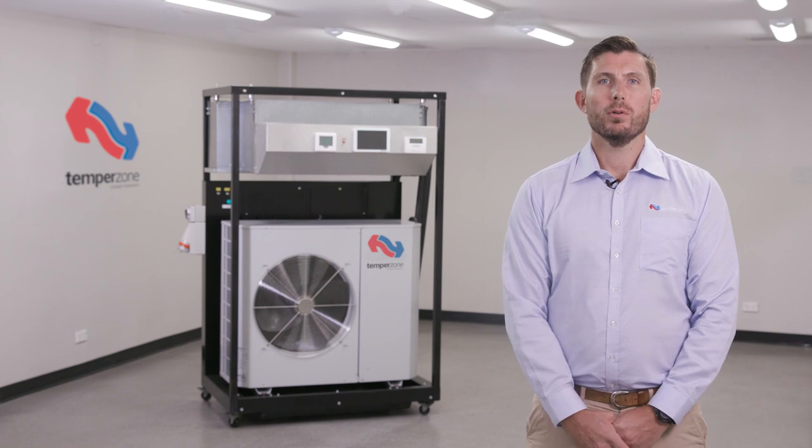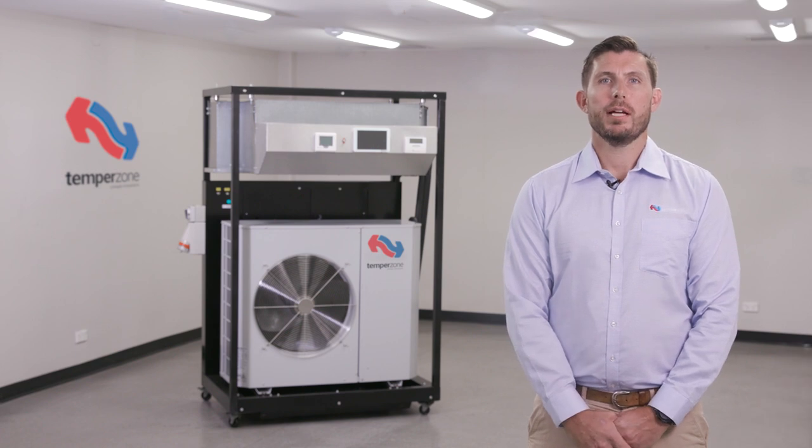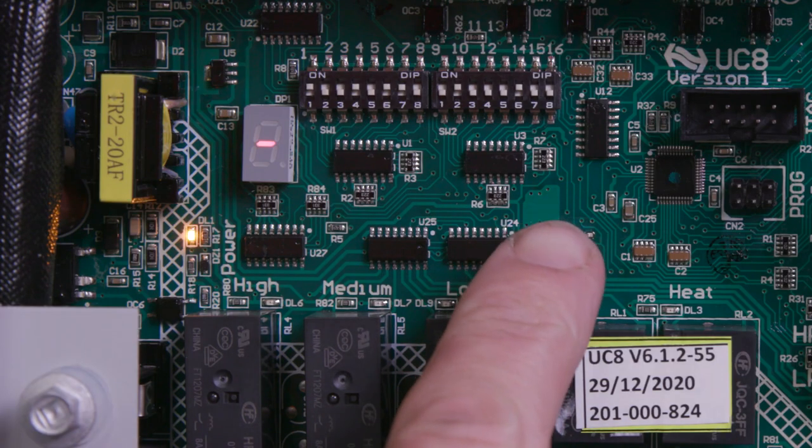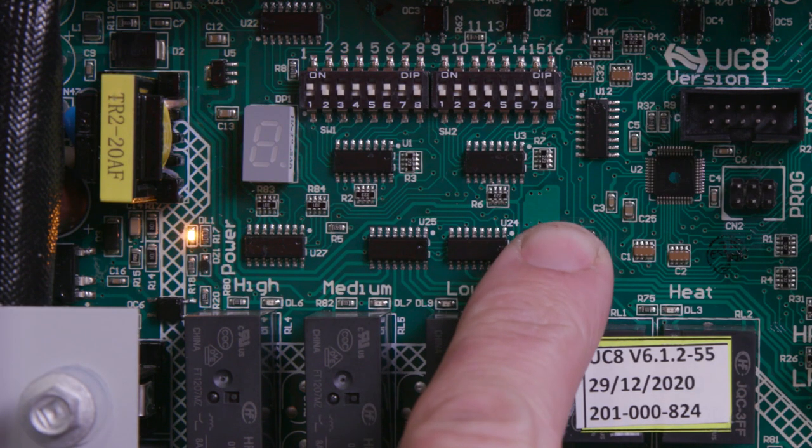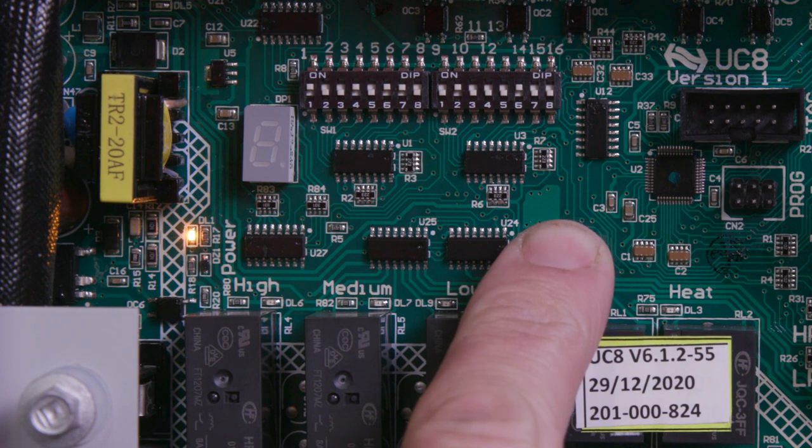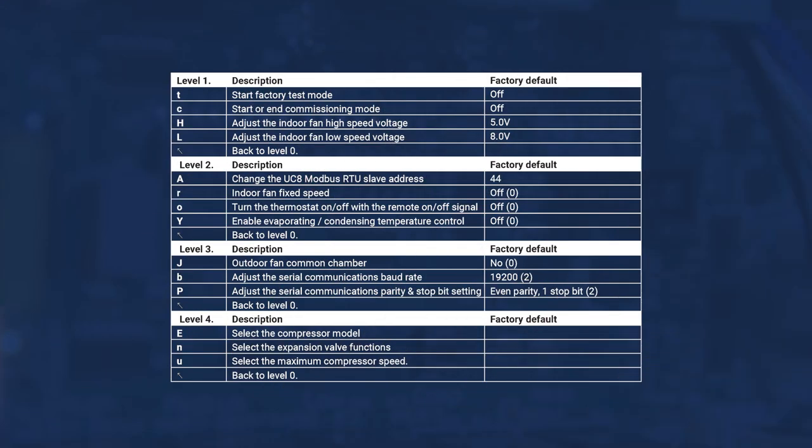The UC8 also has functionality available through the SW3 push button that can assist the installer. These are referred to as special modes. Some of the special modes include adjustment of the high and low fan speed output, Modbus addressing, constant supply air temperature control, and many others. Special mode function and settings can be found in the UC8 manual relevant to your software version.